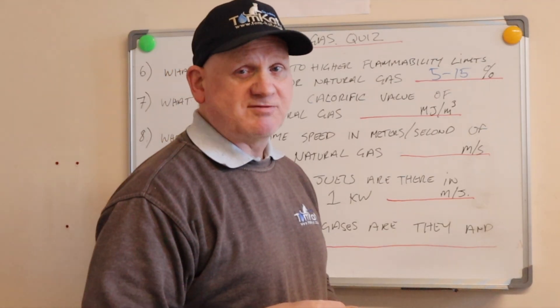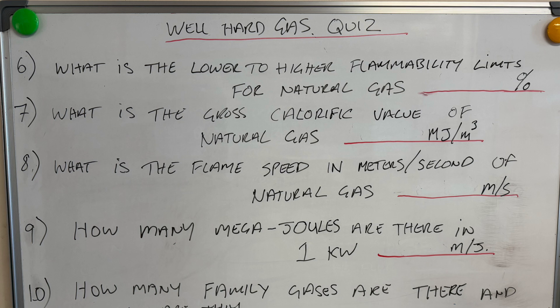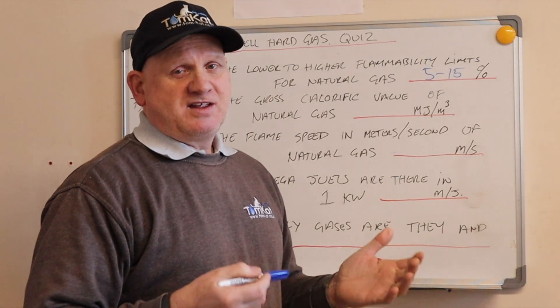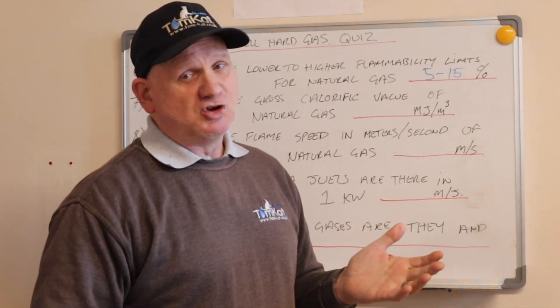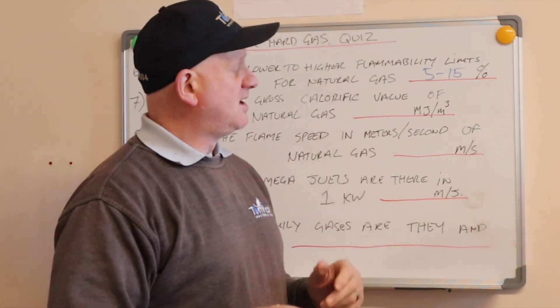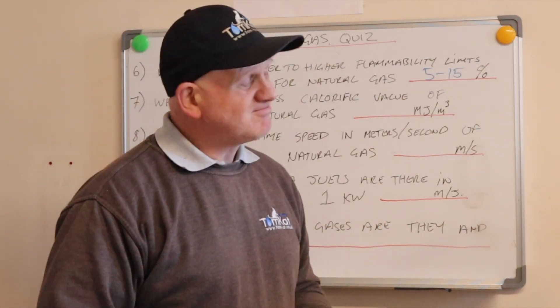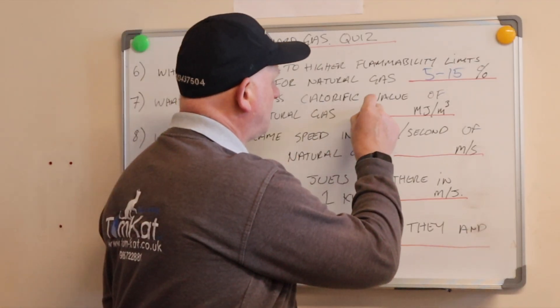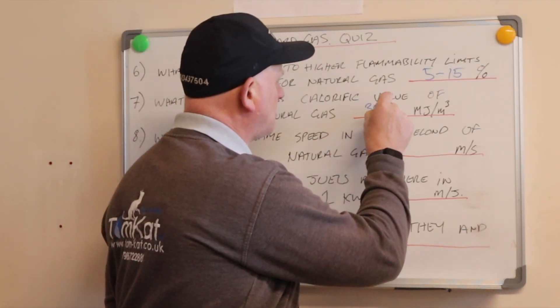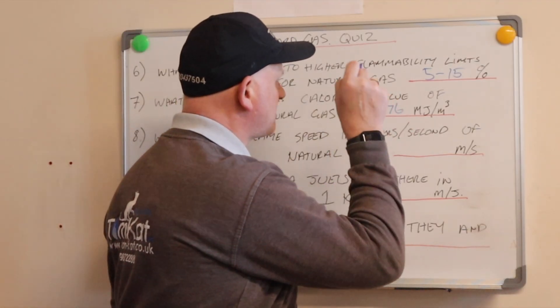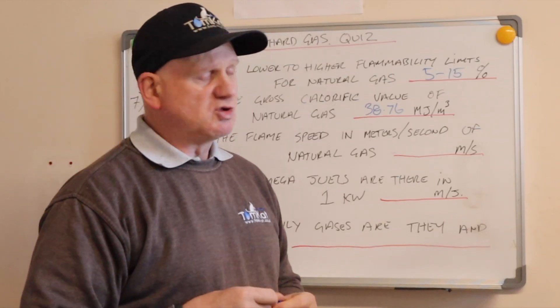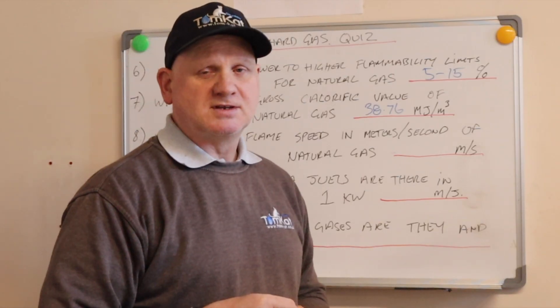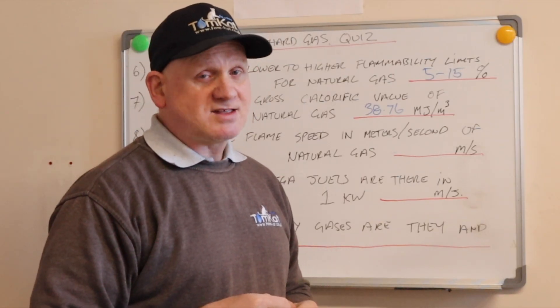Question number seven: what is the gross calorific value of natural gas? If you gas rate the way I show you, you'll know this. It's actually 38.76 megajoules per meters cubed.